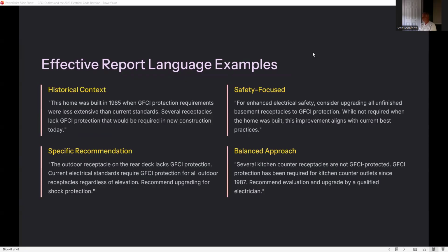Effective report language examples. Historical context: this home was built in 1985, when GFCI protection requirements were less extensive than current standards. Several receptacles lacked GFCI protection that would be required in new construction. Safety focus: for enhanced electrical safety, consider upgrading all unfinished basement receptacles to GFCI protection. While not required when the home was built, this improvement aligns with current best practices. Specific recommendations: we're going to say that the outdoor receptacles on the rear deck lack GFCI protection. Current electrical standards require GFCI protection for all outdoor receptacles, regardless of elevation. Recommend upgrading for shock protection.